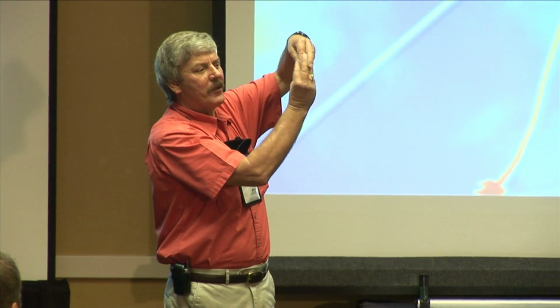The reason it's wound tightly, instead of just loose, especially on high voltage, is to decrease the probability of having electrical discharge. This cable bird caged. It basically came unwound. Have you ever taken a piece of string and unwound it backwards? That's what I'm talking about. It's bird caged. There's electrical discharge going on between the steel outer jacket and the actual aluminum conductor.